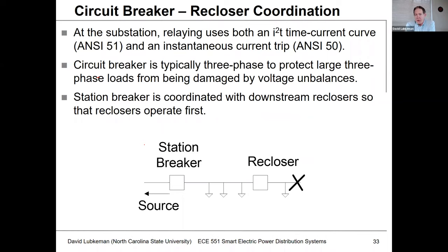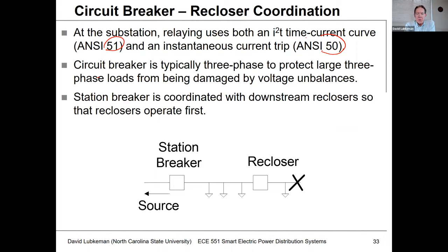For the coordination between circuit breakers and reclosers, we have a substation breaker which is set up for both time overcurrent (ANSI-51) and instantaneous current protection (ANSI-50). The circuit breaker is typically set up to be three-phase ganged — we don't typically have single-phase operation — because large industrial or commercial three-phase customers at the top of the feeder shouldn't be subjected to imbalanced voltage.